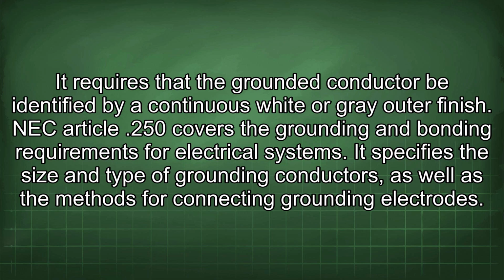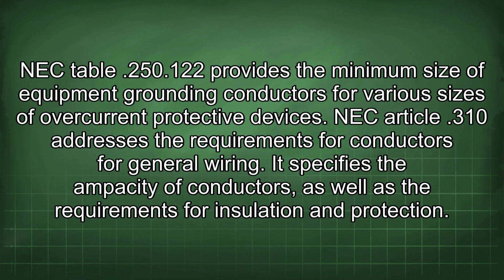NEC Article 250 covers the grounding and bonding requirements for electrical systems. It specifies the size and type of grounding conductors, as well as the methods for connecting grounding electrodes. NEC Table 250.122 provides the minimum size of equipment grounding conductors for various sizes of overcurrent protective devices.